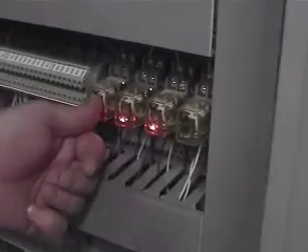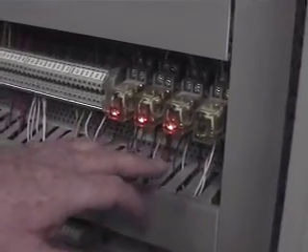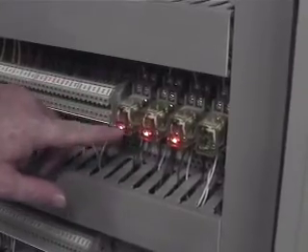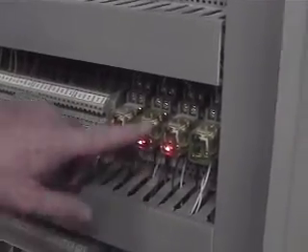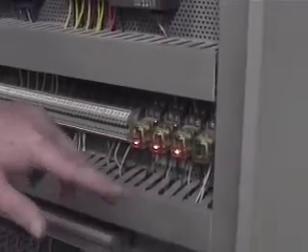One of them, this is your flow switch. I believe this is your high temperature alarm, and this is your emergency switch, I believe. These should always be lit. If you have flow, this one's lit. If your high temperature alarm is not tripped, this one's lit. And if the emergency's not tripped, then it's lit. So generally these will always be lit. If they're not lit, that'll be your first indication.